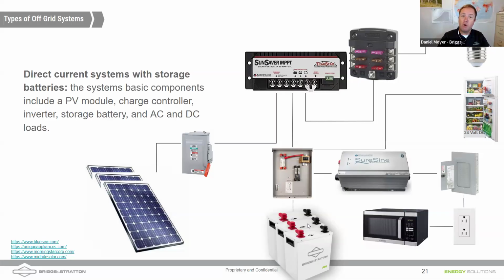So why buy a battery and pay extra for one that does, when we can simply program the bulk, the float, the absorb, disable, equalize settings, make sure we get the charge and discharge currents dialed in correctly, and make sure we have enough batteries so we don't exceed the C rate of the batteries? Go ahead and leverage these batteries.